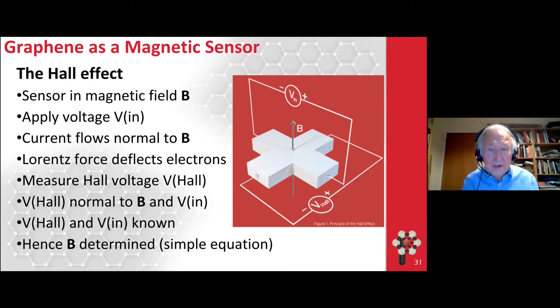How are Hall sensors used? They're used for measuring magnetic fields, but also for measuring currents in wires. If you have a wire or cable carrying an electric current, a magnetic field is generated around that cable, and you can use the Hall effect sensor to measure the magnetic field and therefore determine the current in the wire. It's a non-contact way of measuring currents in wires.